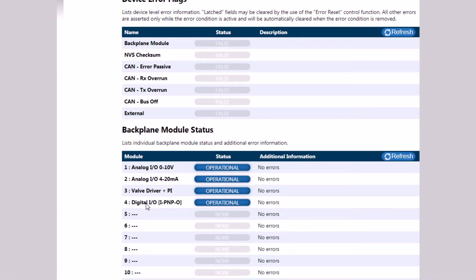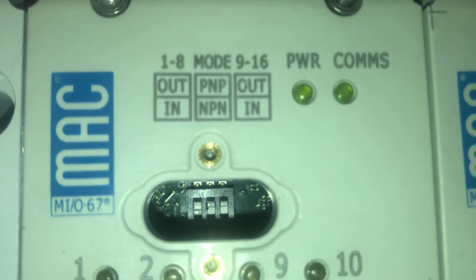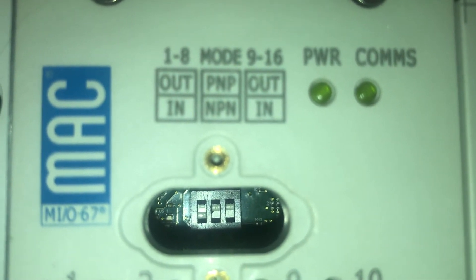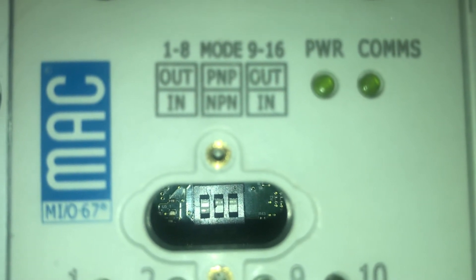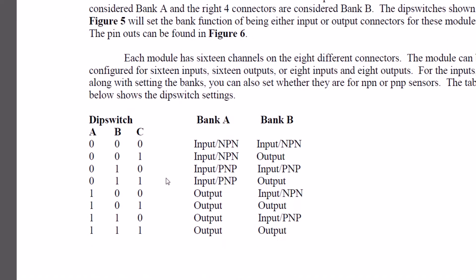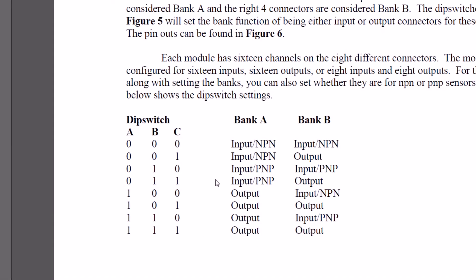We will also need to determine the type of digital I/O module that's been configured using the dip switches. The web config utility has identified that this module is set up for PNP input and output. You can also determine that by looking at the dip switches inside the module. The dip switches are set 0, 1, 1, which indicate a PNP input configuration for bank A and a PNP output configuration for bank B. This will be important later when we select the right config module setting in the AOI.